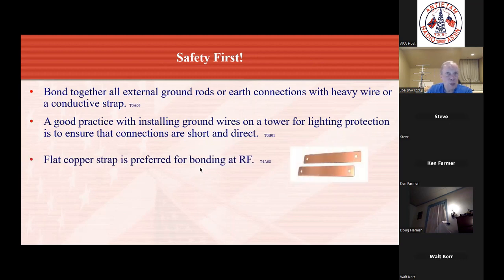Flat copper strap is preferred for RF bonding, and you can see they've got some examples of it there. Those are just flat pieces of copper. Lots of surface area, and that is a real benefit when you're talking about grounding, even more so than wire.